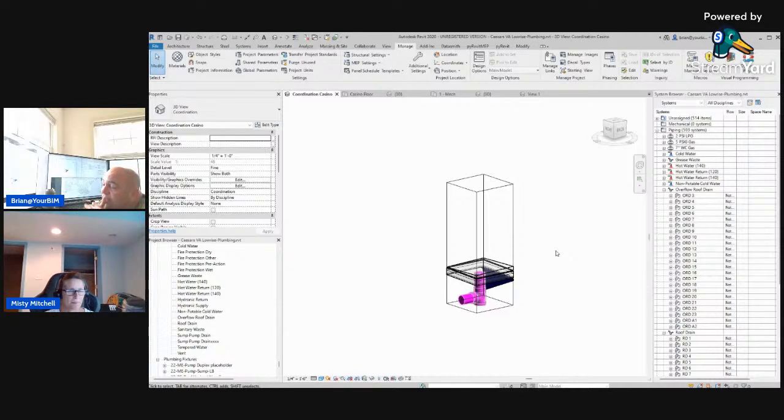But you know what I would call the vents? Just like you're doing the drains. The first restroom vent through the roof is going to be A1. The second vent through the roof is going to be A2. The VTR, the vent through the roof, is probably going to control all the bathroom area in that system. So the vents should be named area A1, area A2, whichever area they pop up in. Does that make sense?